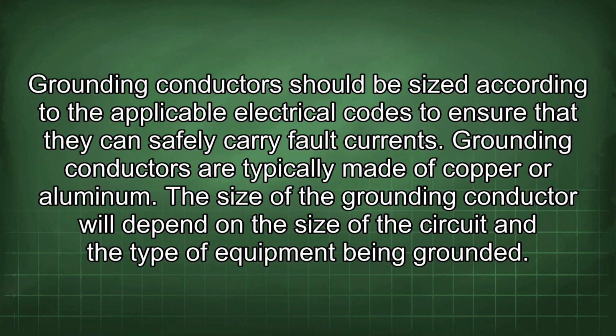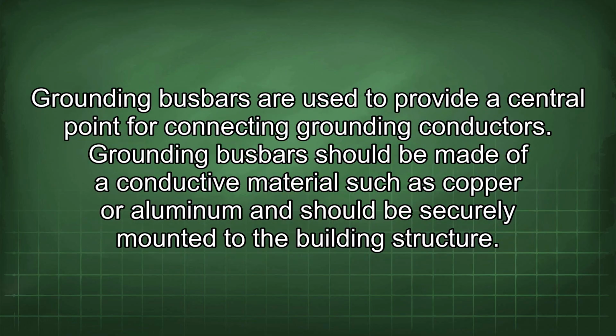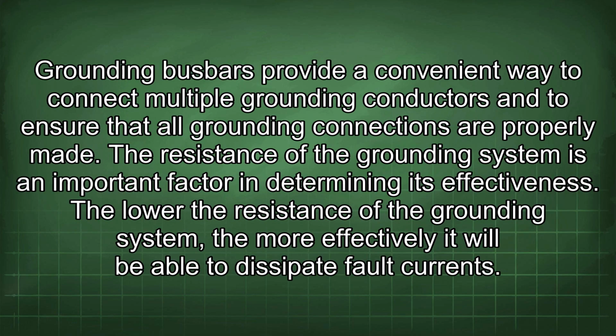Grounding conductors should be sized according to the applicable electrical codes to ensure that they can safely carry fault current. Grounding conductors are typically made of copper or aluminum. The size of the grounding conductor will depend on the size of the circuit and the type of equipment being grounded. Grounding busbars are used to provide a central point for connecting grounding conductors. Grounding busbars should be made of a conductive material such as copper or aluminum and should be securely mounted to the building structure.